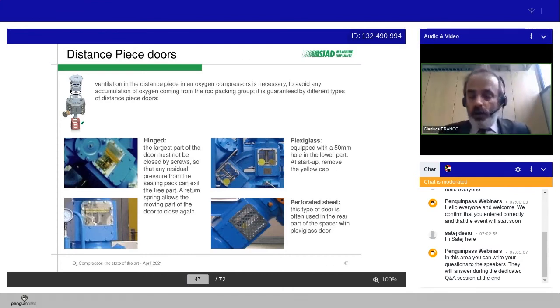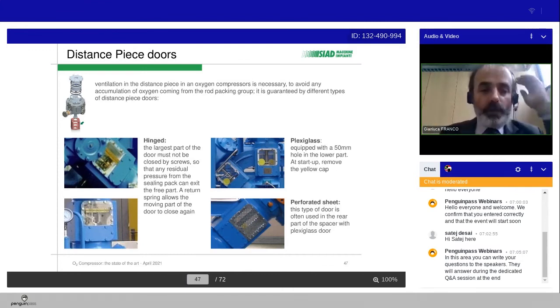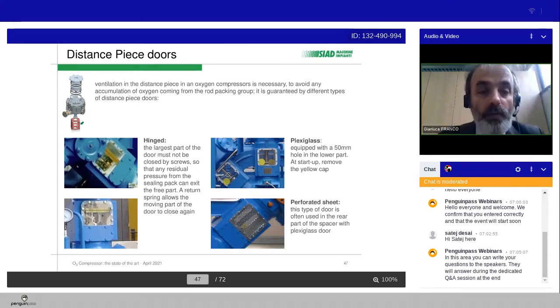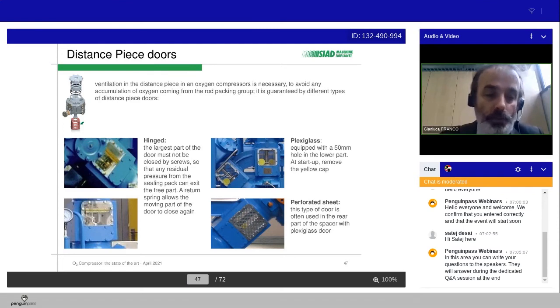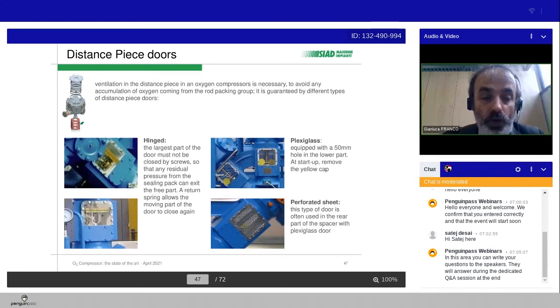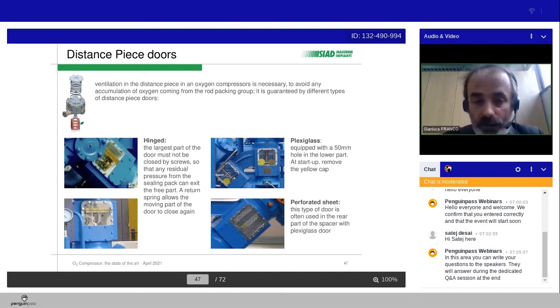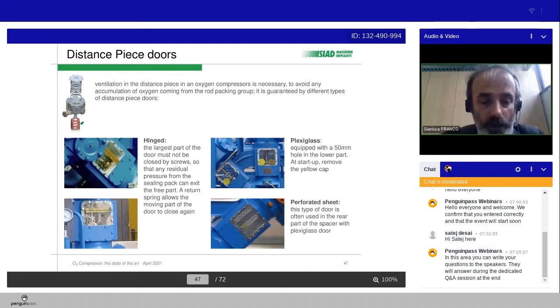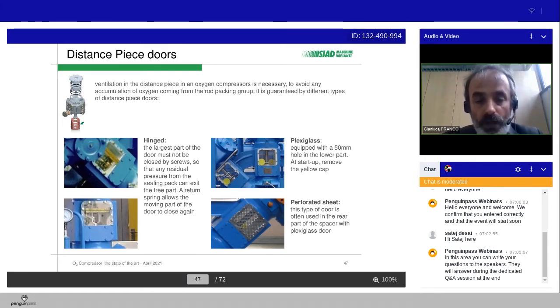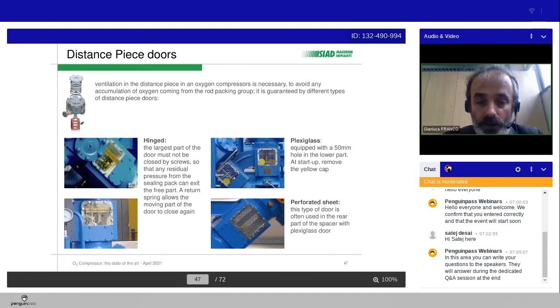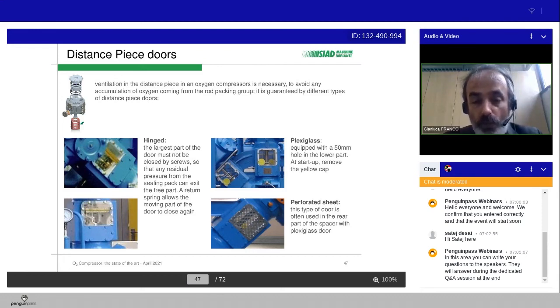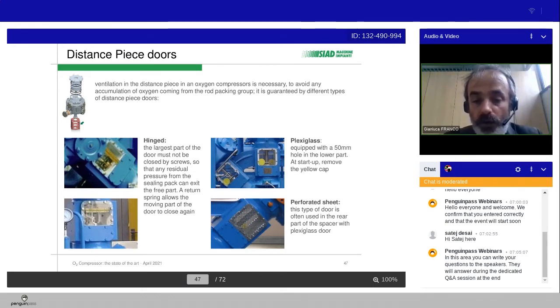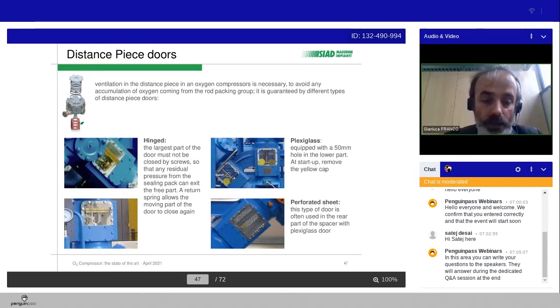Additionally, the distance piece for an oxygen machine is equipped with special doors. We have typically three types of doors. Hinged, the largest part of the door must be not closed by screw, so that any residual pressure from the sealing pack can exit the free part, and a return spring allows the moving part of the door to close again. We can have plexiglass. Typically, we have a cap here, 50 millimeters, that must be removed at the start-up, or perforated sheet that is often used in the rear parts of the spacer with the plexiglass door.